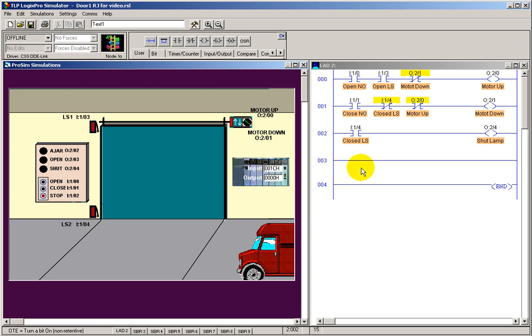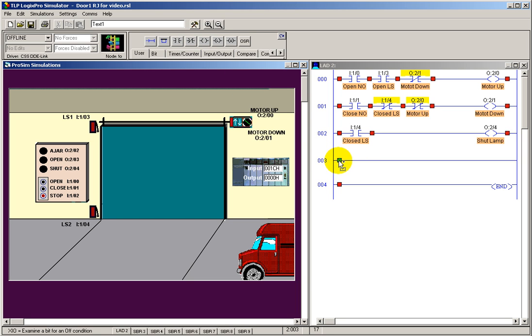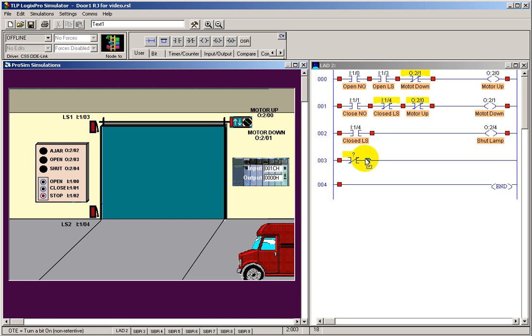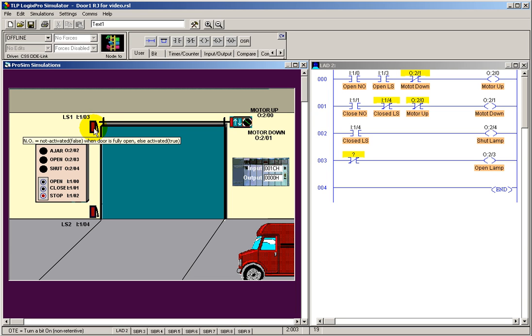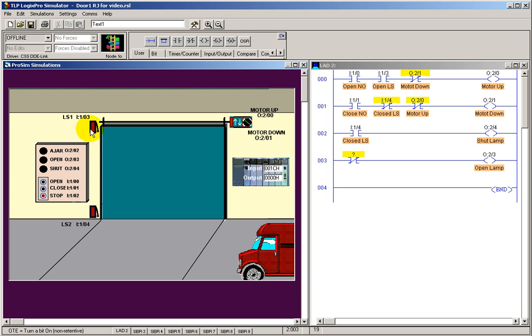Let's put the closed limit switch address up here. Now we're going to use the open limit switch to energize the open lamp. This is going to be the opposite though. This is going to be when I'm open, when this limit switch is open, is when I actually want to indicate that this open lamp should be energized. That should make sense, right? Almost all the time, this guy's activated because the door isn't open. When it fully opens, it's no longer activated, which would satisfy this condition here. Let's put this limit switch address in here.